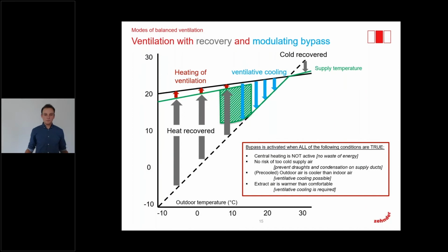Let's go a little bit further. Now we can see what happens if we use a modulating bypass. On the left-hand side, you can see the heat recovery. It's the same as before. On the right-hand side, you can see the cold recovery. It's also the same. Now we take a look at the area in between. Let me start with the blue arrows. There we have a potential outside because the outdoor temperature is below the inside temperature and we have a need for cooling. So what we do is open the bypass and let in the air. This is ventilative cooling, or you could also say free cooling.